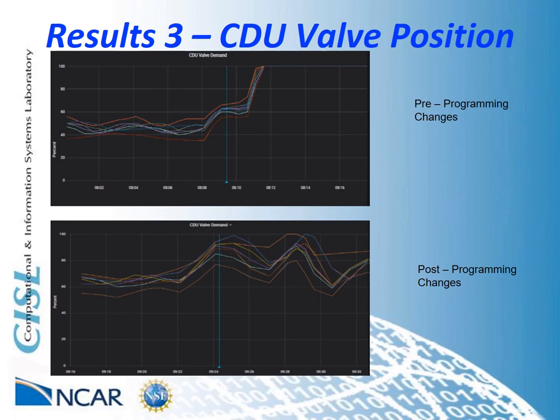The final set of results relates to the CDU valve position. During the original sequence shown on top, the valves would skyrocket to 100% and stay there for some time to try to evacuate as much heat as possible from the system. In the lower graph that shows our transition post changes, the valves open to 100% but only momentarily, proving that the heat is dissipating from the CDUs more efficiently after the change.